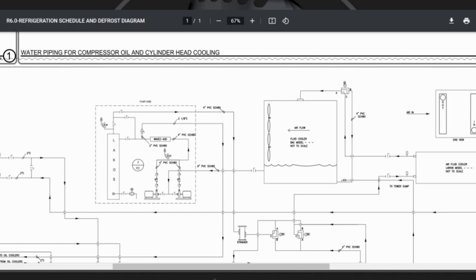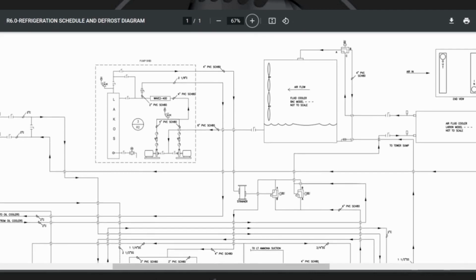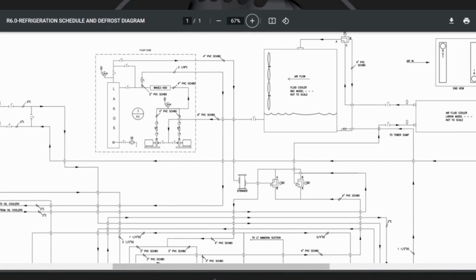Yeah. And remember, ammonia is not like propane or halocarbon or synthetic refrigerants, it's lighter than air, except on a rainy or foggy day. So it vents and it goes up. It doesn't come down. So you talked about having reliefs on the system, and as far as controlling the head pressure, you do have the air fluid cooler and the BAC, so you have a little bit of redundancy there that you can utilize. Yes, but if we lost the circulating pumps, if we lost both pumps, we'd be down. Wouldn't matter how big, we'd be in trouble.